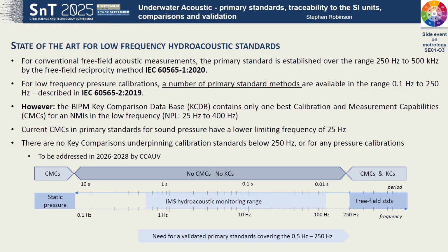There are a number of international standards for how to go about doing primary measurements, IEC 60565 being the basic one. Most of the measurements done at kilohertz and even down to 250 hertz are free field measurements, so you're measuring large volumes of water. But at low frequency, we tend to use a different calibration method called pressure calibration, which I'll explain a bit about in a minute. And that's actually where traceability is weakest, because we haven't done some of these comparison exercises yet to compare the different standards.